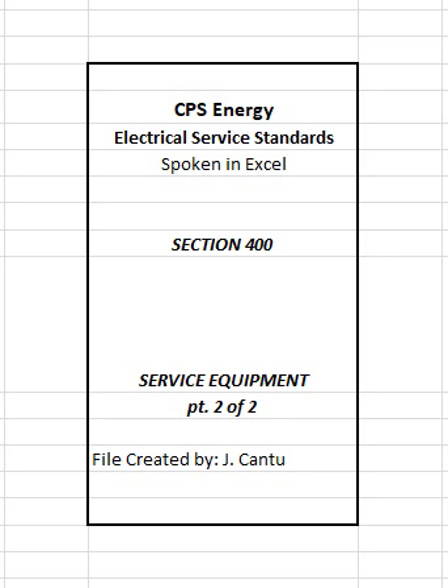409 Meter disconnects for distributed generation. On all distributed generation (DG) systems, a meter disconnect switch shall be installed ahead of CPS Energy's kilowatt-hour meter to isolate it from the DG power source. The meter disconnect switch shall be located immediately adjacent to the meter, refer to section 2000.